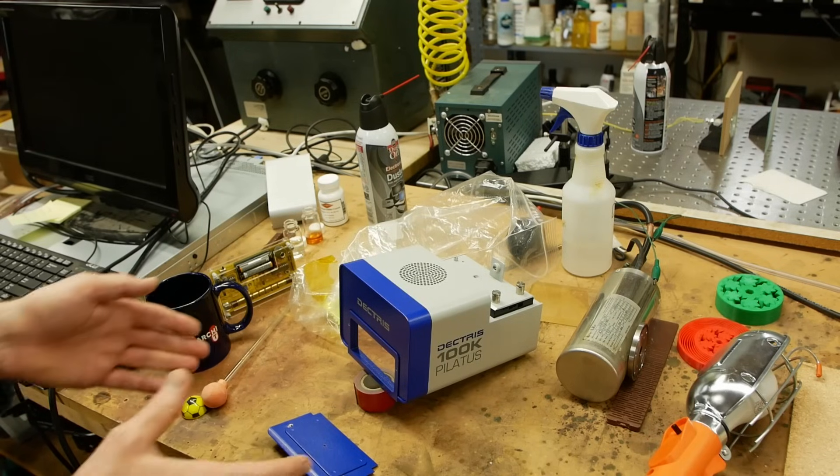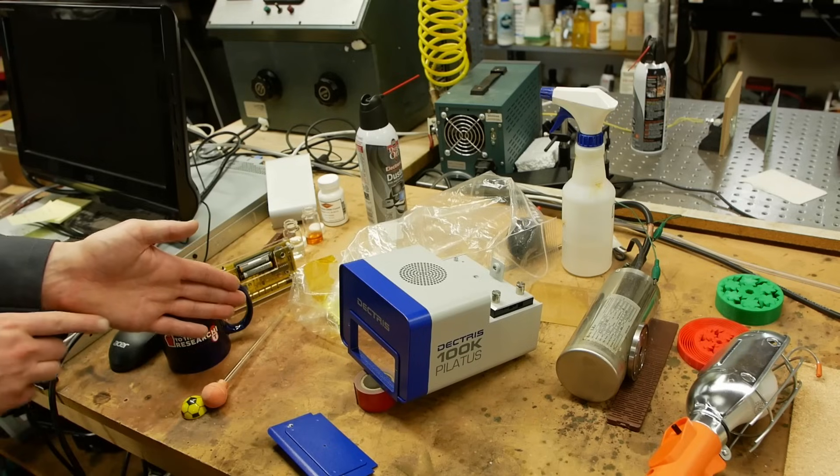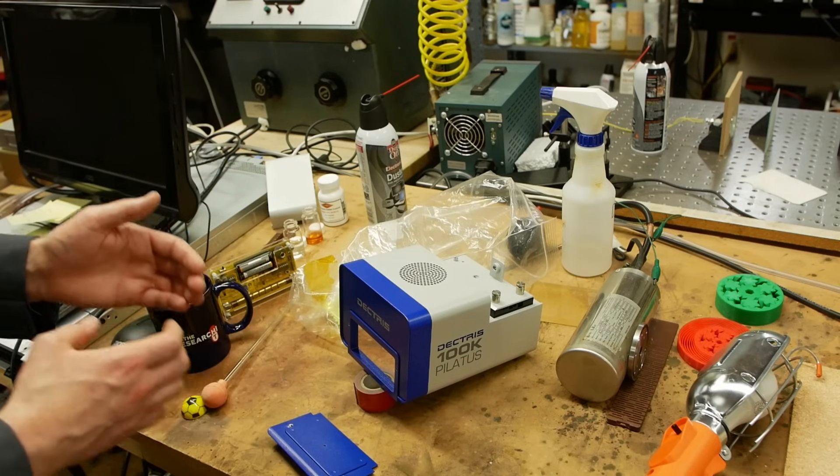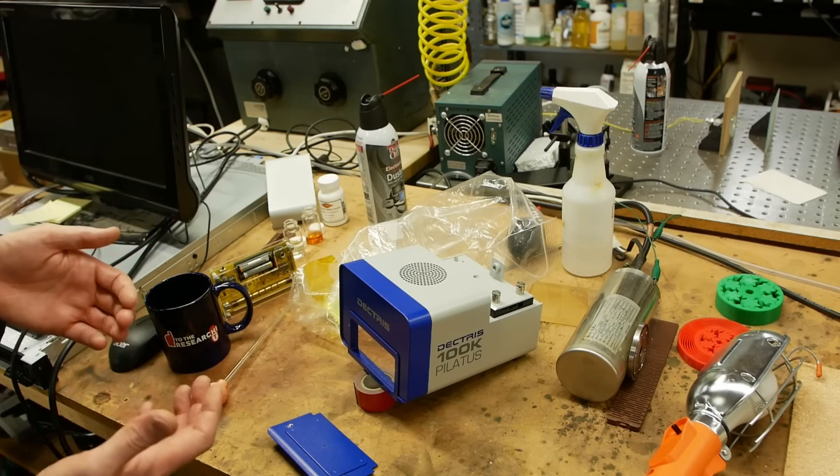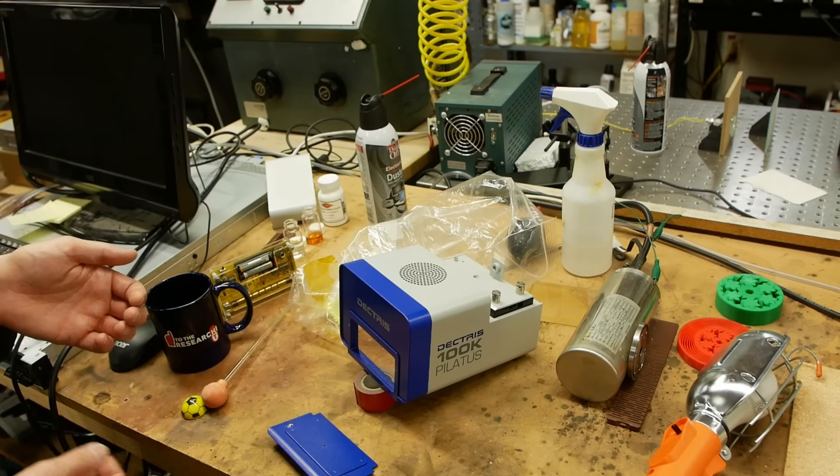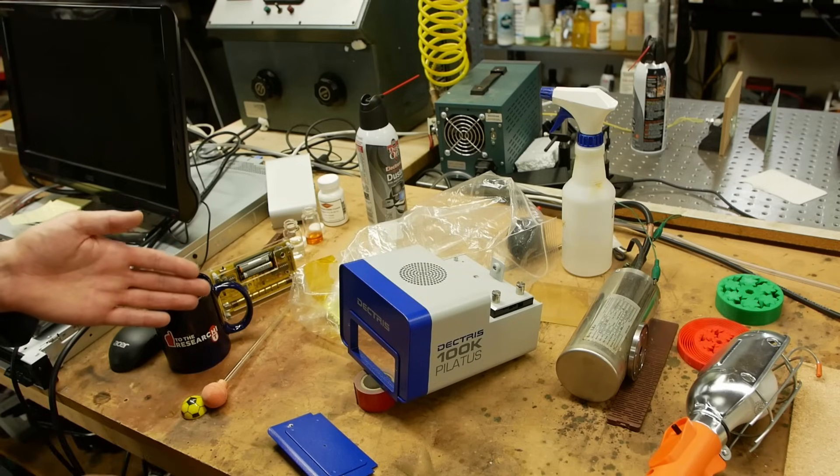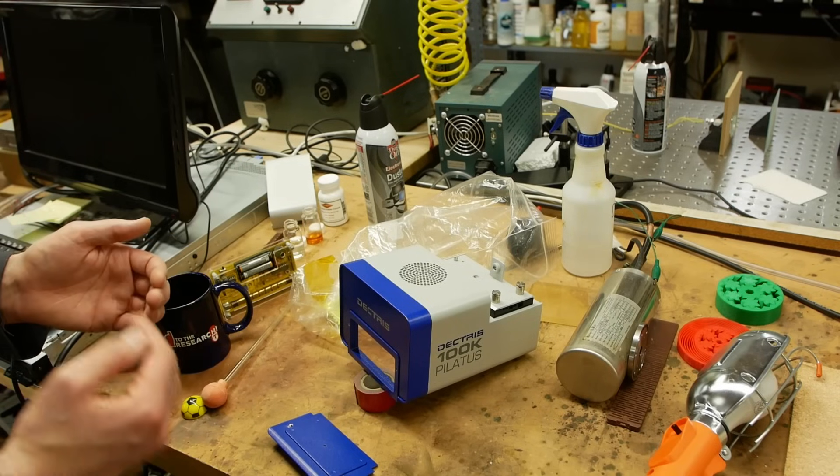So the way this works is it's a direct conversion sensor. So when an x-ray photon goes in, there's a semiconductor that's specially tuned to catch x-ray photons between 5 and 30 kilo electron volts. And when the photon goes in, there's a chance that it is instantly converted into a digital pulse. So it just counts photons.